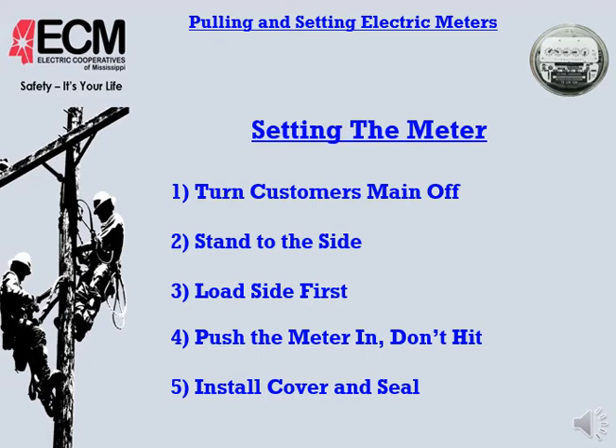First thing we're going to do when we get ready to set a meter is try to turn the consumer's main off. Now, granted, there are some cases where you just can't get to the consumer's main to do that. That's one reason why we have our PPE, and one reason why we do our inspection process. But if you can get to the consumer's main and cut it off, that's going to eliminate a lot of the potential backfeed problems you may have when doing the voltage check.